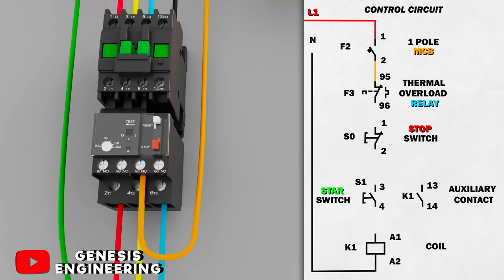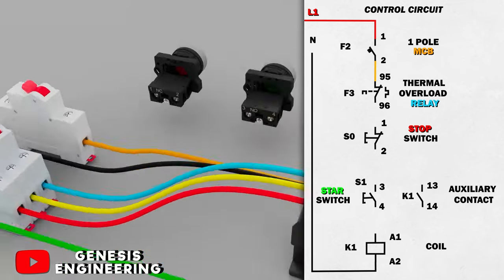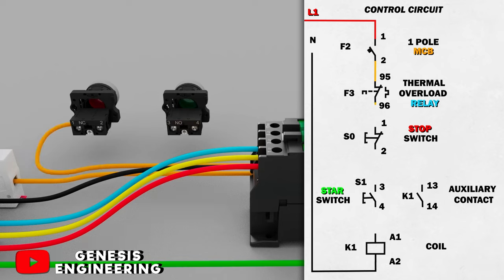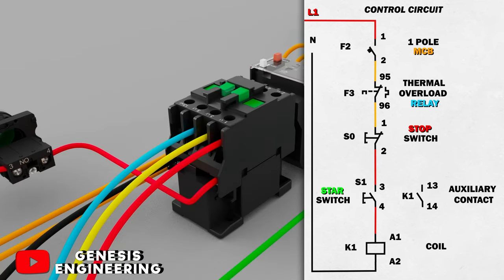Then we go out with the conductor on terminal 96 of the thermal relay and connect it to terminal 1 of the normally closed red button. In the output of the red button, terminal 2, we connect to terminal 3 of the green button, and we leave terminal 4 of the green button and connect to A1 of the contactor.